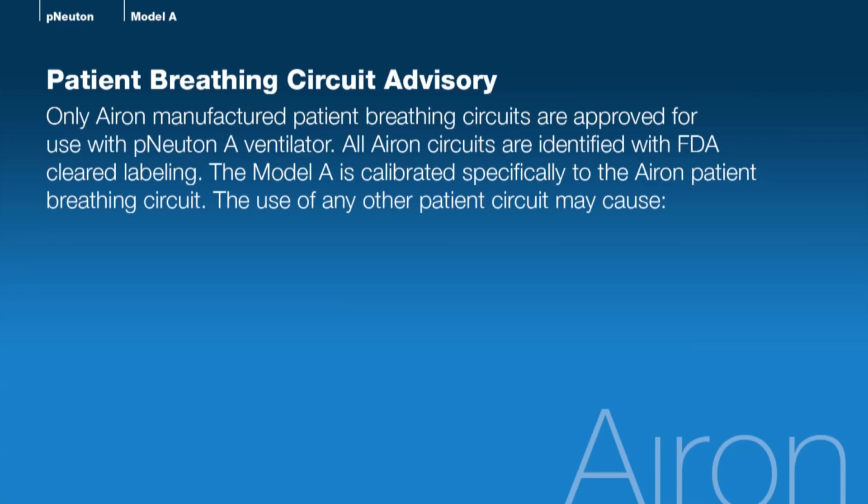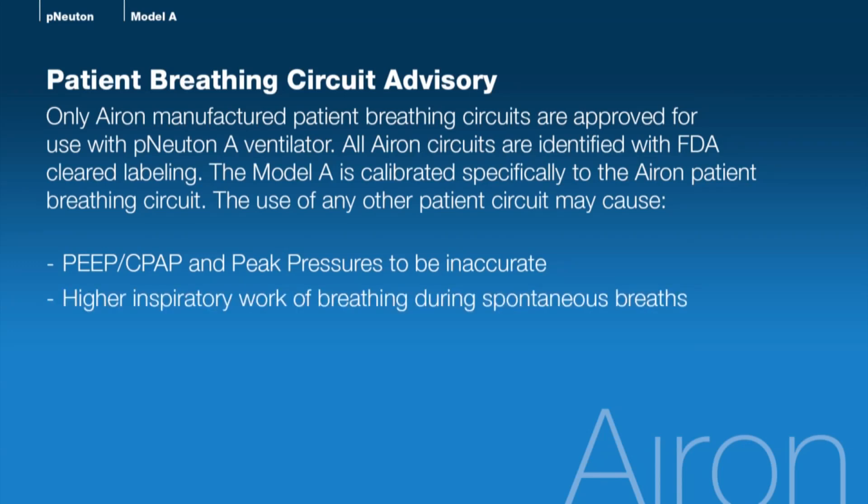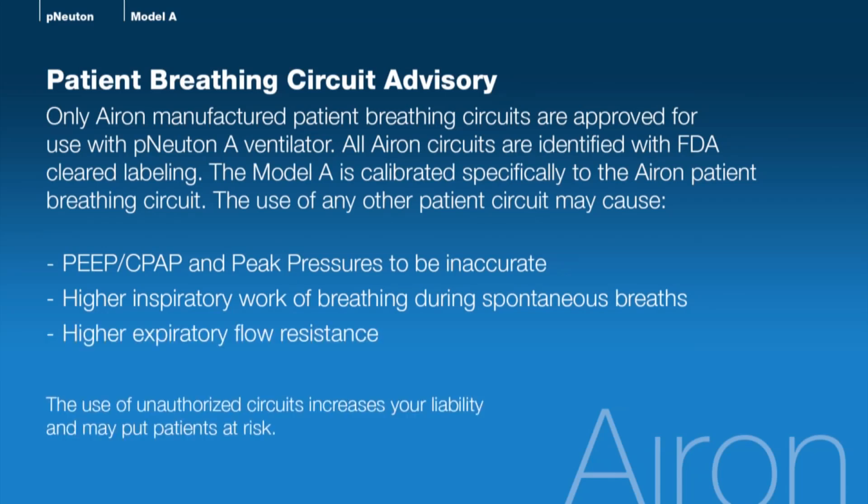The Model A is calibrated specifically to the Airon patient breathing circuit, and the use of any other patient circuit may cause PEEP/CPAP and peak pressures to be inaccurate, higher inspiratory work of breathing during spontaneous breaths, and higher expiratory flow resistance. Our patient circuits are competitively priced. The use of unauthorized circuits increases your liability and may put patients at risk.